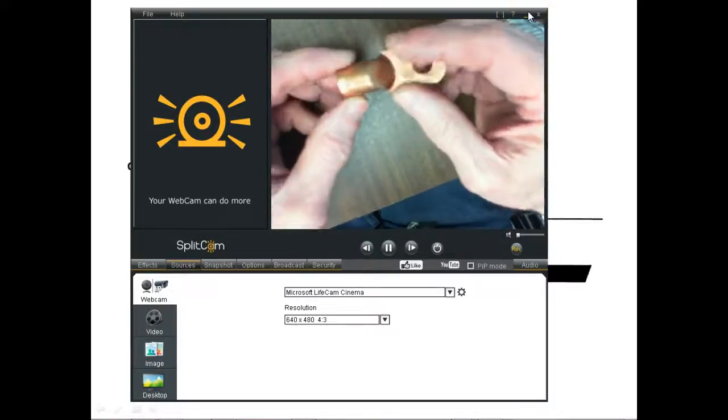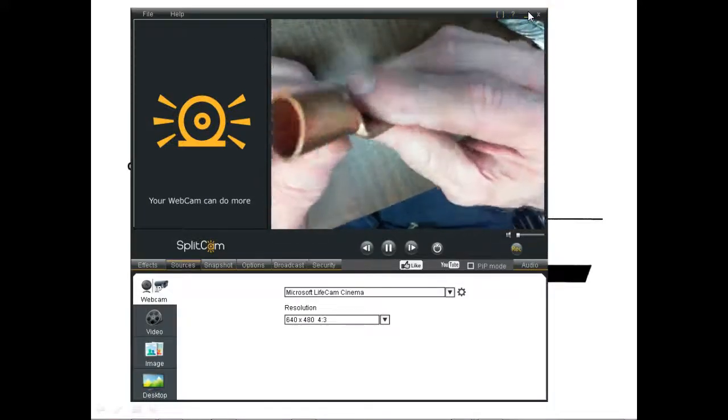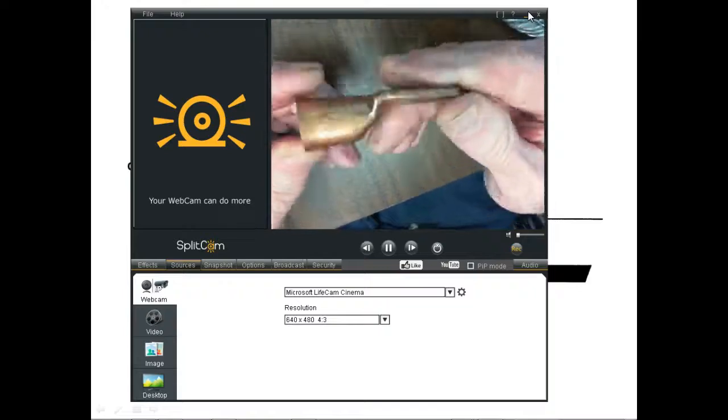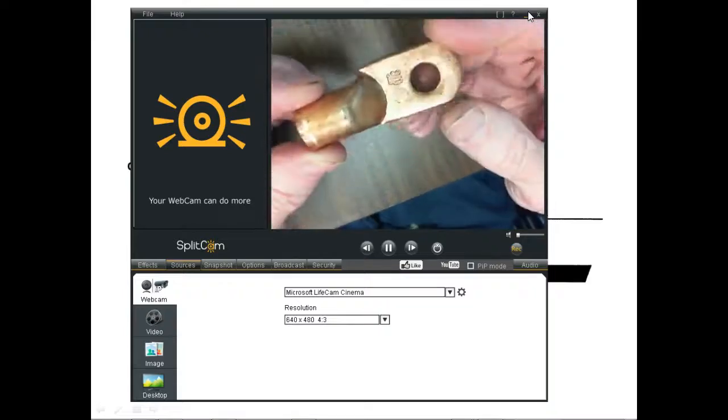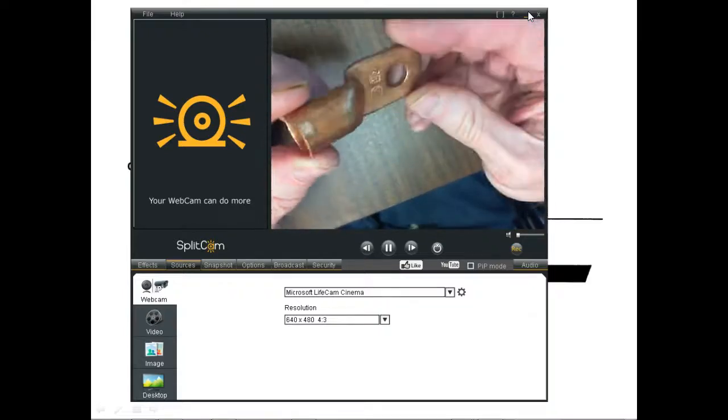But this is a crimp splice. Some of these crimp splices are hydraulic, or you'll see them with big long handles, or a hydraulic one where you put it in there and pump it to crimp them. You're not going to crimp those with a standard crimper, that's for sure. It's just like this. This is a crimp terminal here. You're going to have a special crimper to crimp this, right? So this would be a crimp terminal.